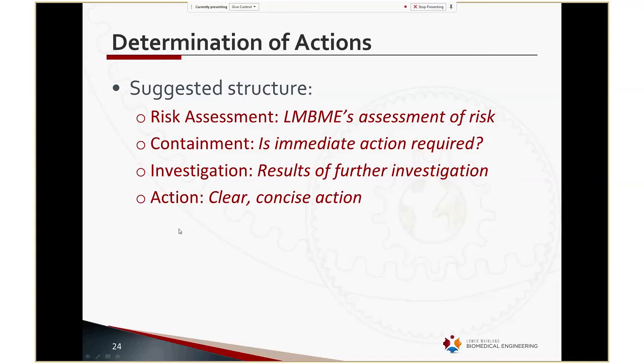Containment. So containment concerns any sort of immediate action that might be required. So this would be quite rare. This would include anything that might warrant an immediate response. So something where, let's say, there's an alert that comes out on the ventilator, we read it and we think, okay, those ventilators are not safe for use for patient care. We need to go out, inform clinical staff, and come up with a plan to get them off the floor. So we weren't able to actually come up with any examples from recent history where containment was required for an alert.